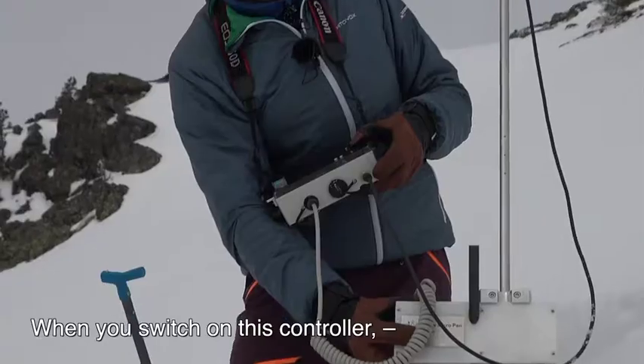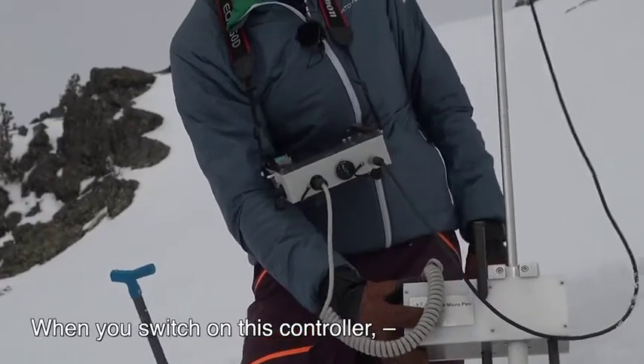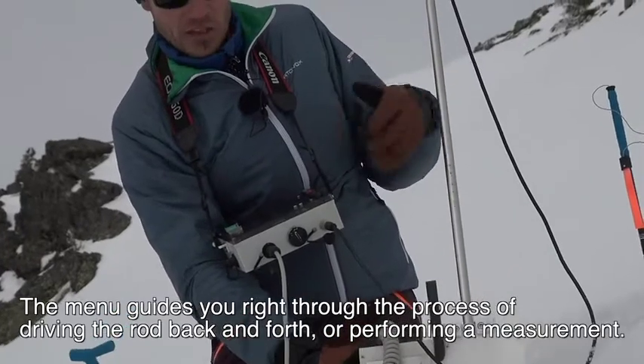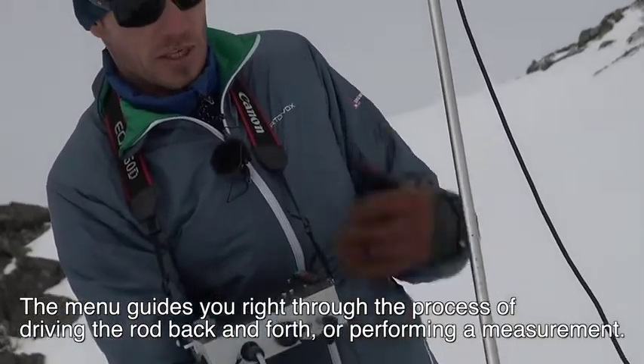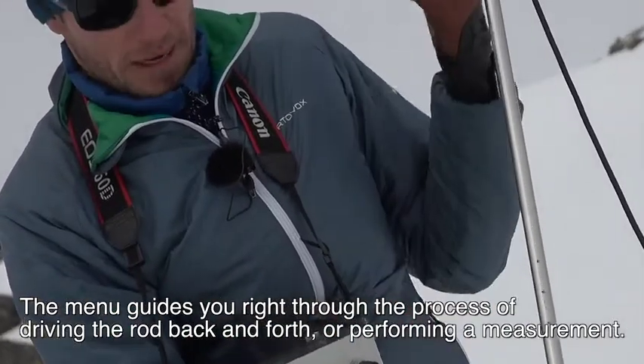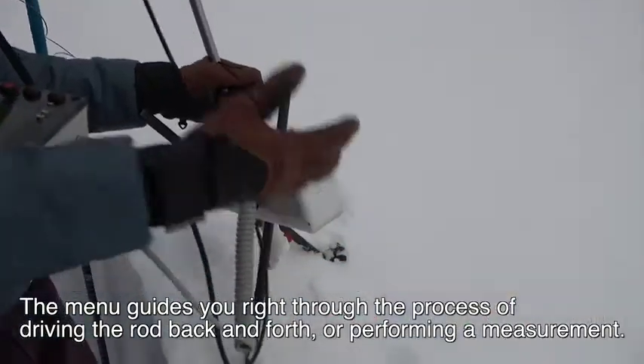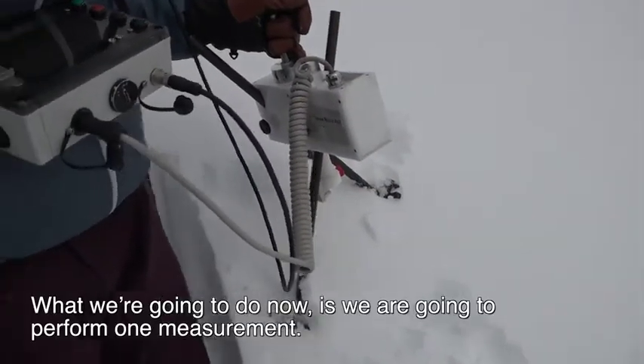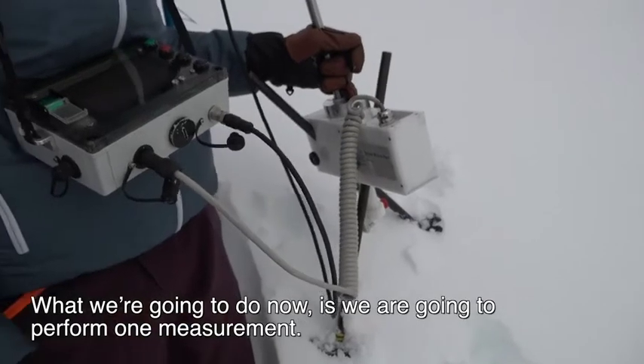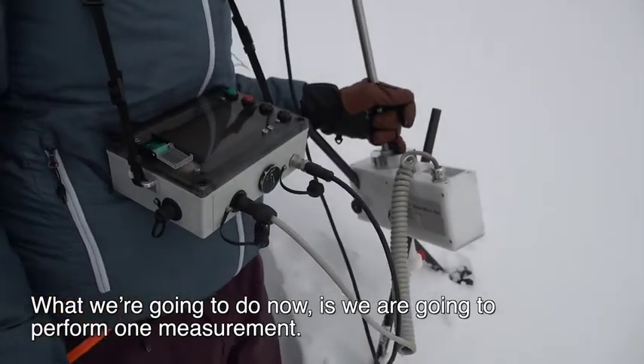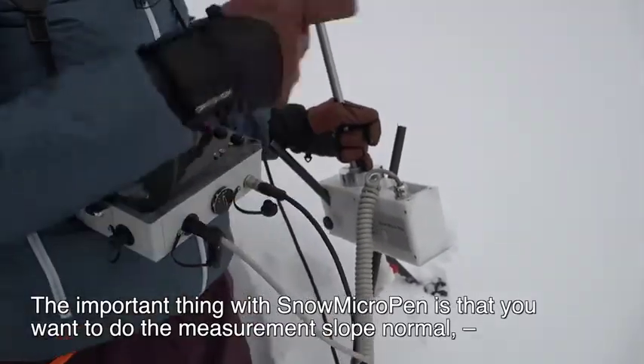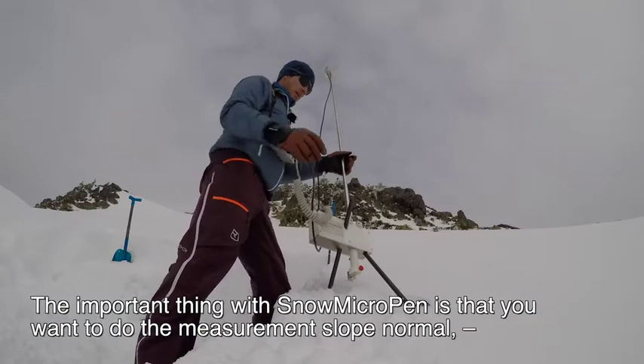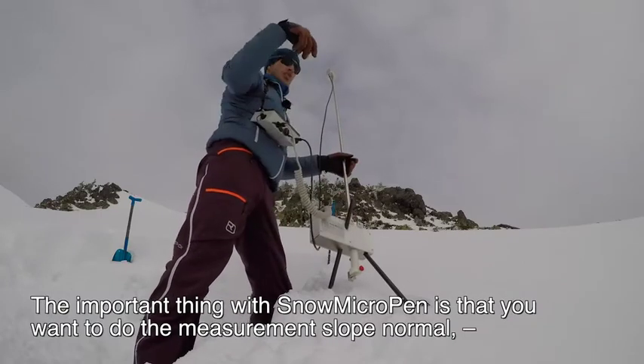So when you switch on this controller, the menu guides you right through the process of driving the rod back and forth or performing a measurement. And what we're going to do now is perform one measurement. The important thing with the Snow Micropen is that you want to do the measurement slope normal.